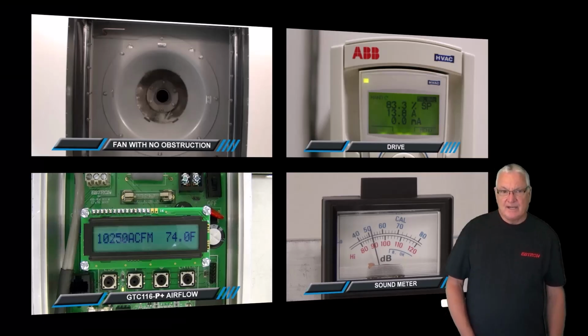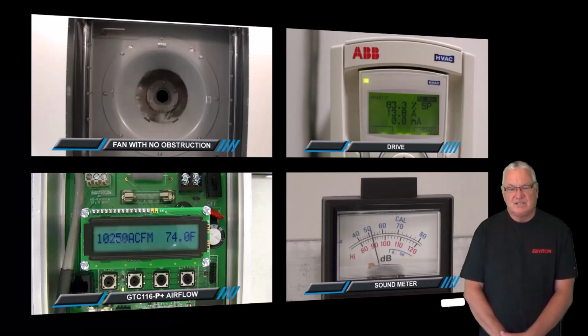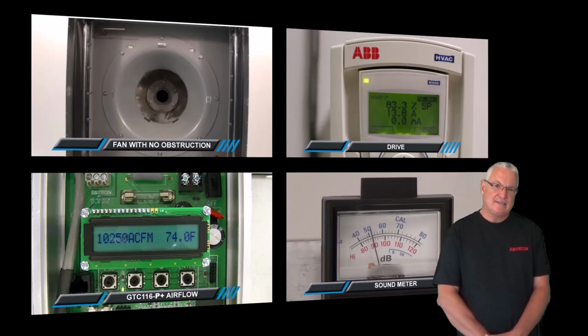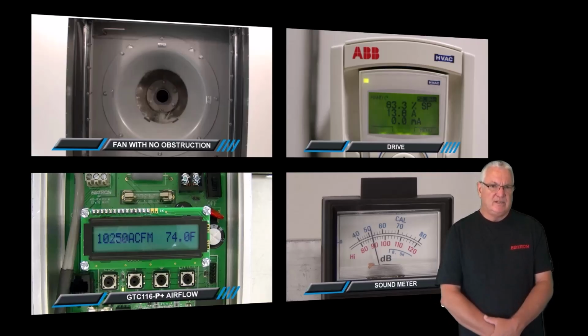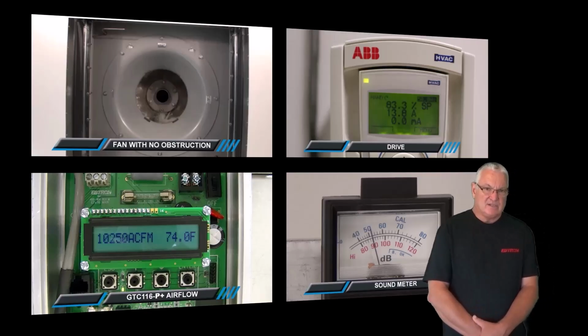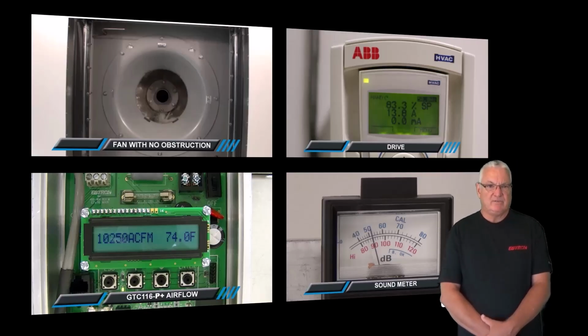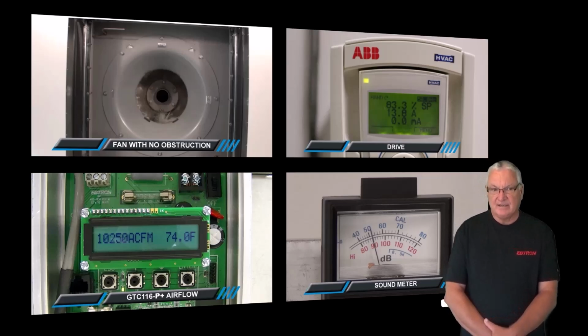All right, don't let anybody tell you that these devices affect fan performance because they do not. Okay, this is a plenum fan. This is a Greenheck plenum fan, QEP24 model. And if you look at each one of these screens, what you see is you'll see the fan with no obstruction, top left. You'll see what the drive output is, and the current draw is what I'm particularly interested in. On the top right, so it's 13 amps there. The flow that you're seeing on the bottom left is the flow as measured downstream of the fan in the duct. So we're not measuring it in the fan in this case.